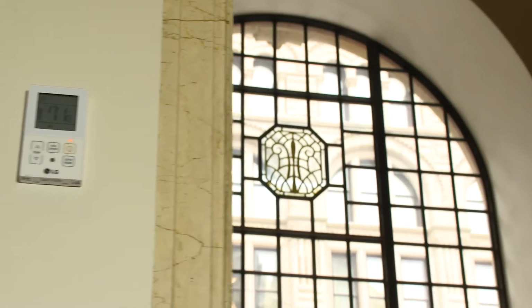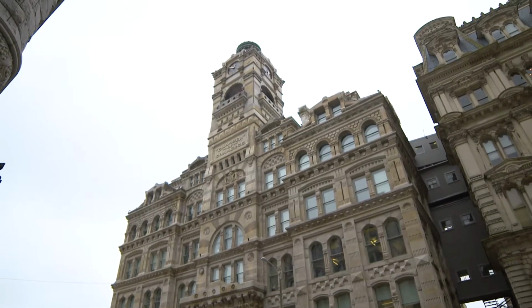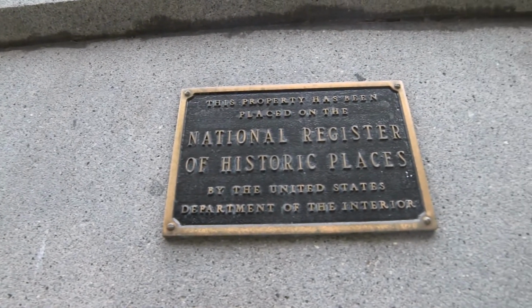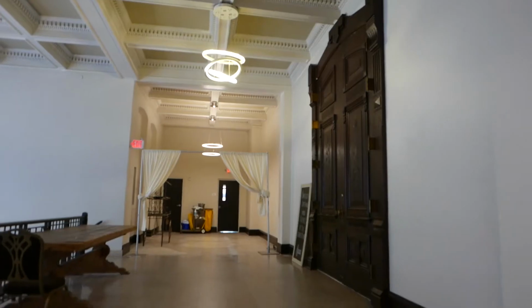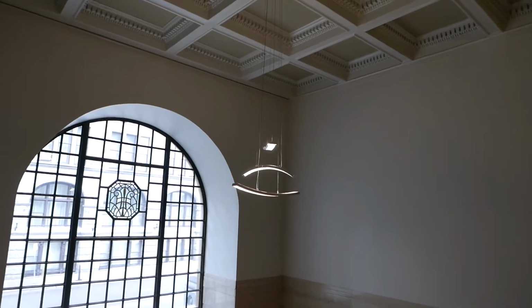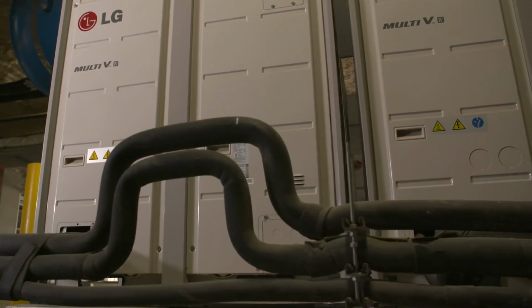The system is very conducive to being retrofitted into an old building. We were able to zone each floor, zone each unit, however we needed to accommodate those different uses. We had to be careful on the project. There were requirements from the National Park Service for the historic rating of the building. Walls are 2 to 3 feet thick. Floors are wood in some areas, concrete and stone in others. It's very difficult to route large ductwork or large piping systems throughout the building. So VRF is perfect in the fact that I'm not running large ductwork through the ceiling. I now have just maybe 1.5 inches of pipe that's going to be running throughout the space. So that gave us the flexibility that we needed.